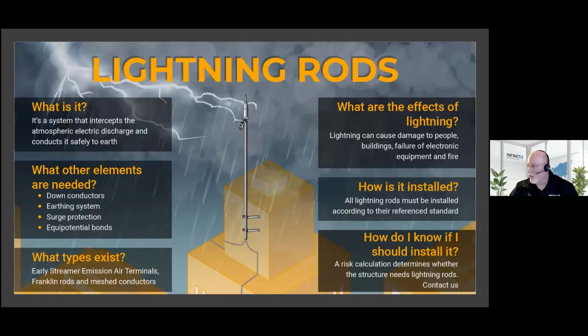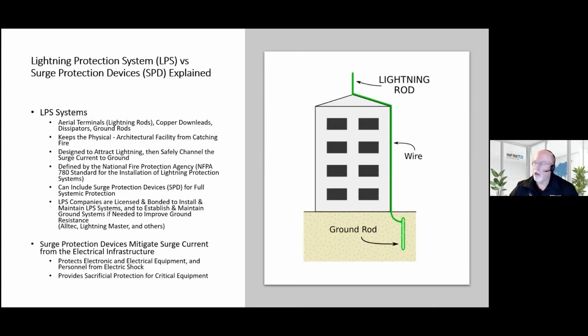Oh, about LPSs, there are companies that are LPS companies. They're certified, they're bonded, and they're grounding experts as well. So let's say somebody wants to find out what the ground conductivity is at a location they're going to install a transmitter, for example. Then an LPS company can do that. They'll bring out test equipment. They'll test what the ground resistivity is. If it's within whatever good parameters, then great. If it's not, then they will create ground wells.